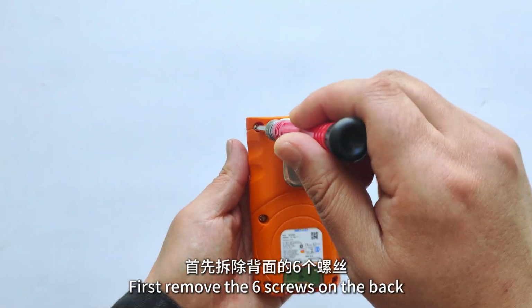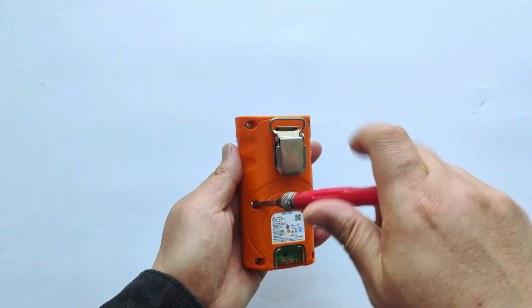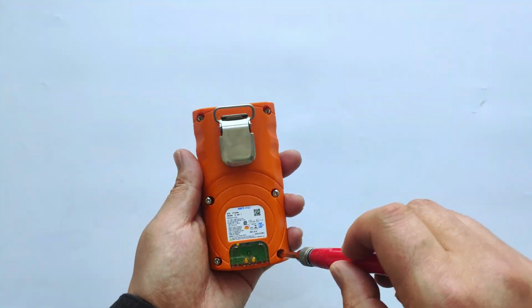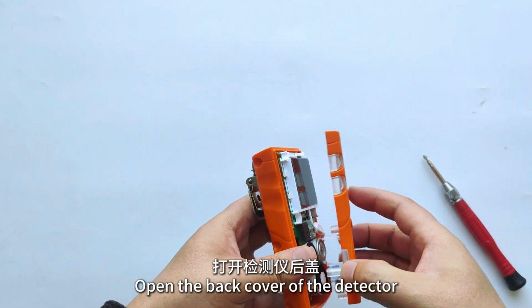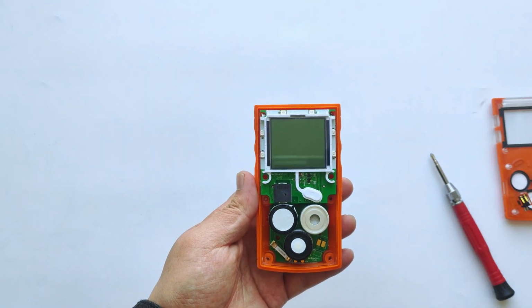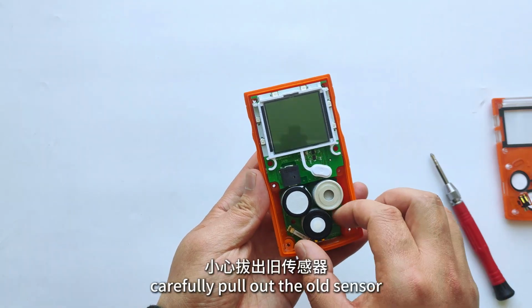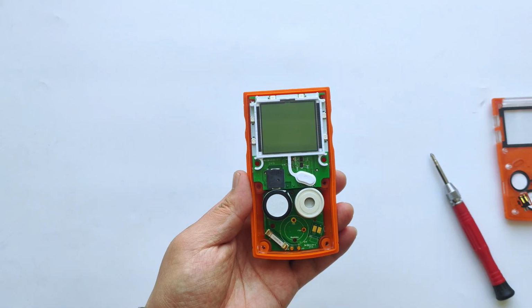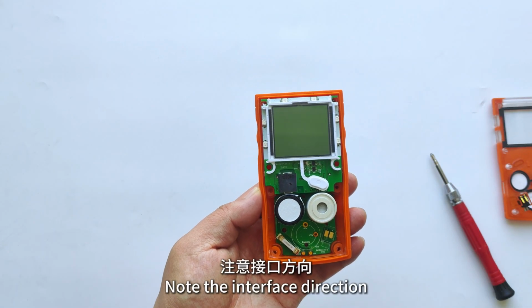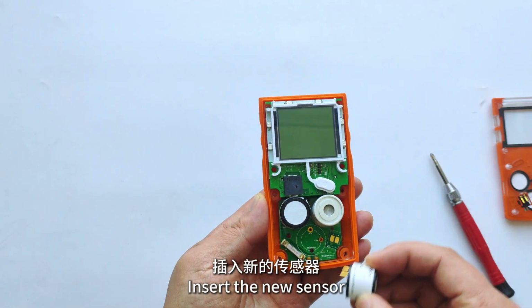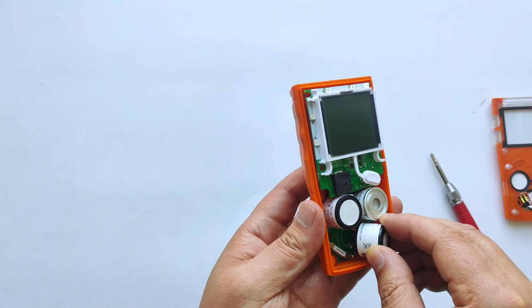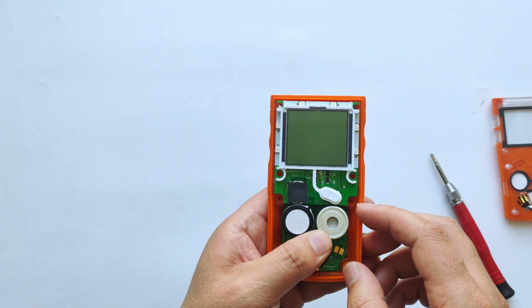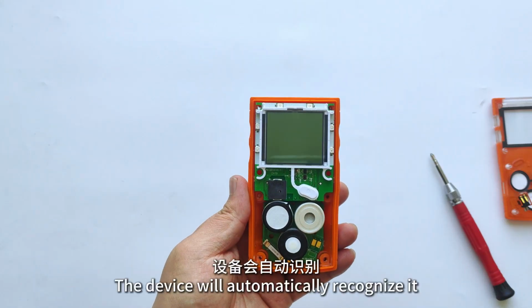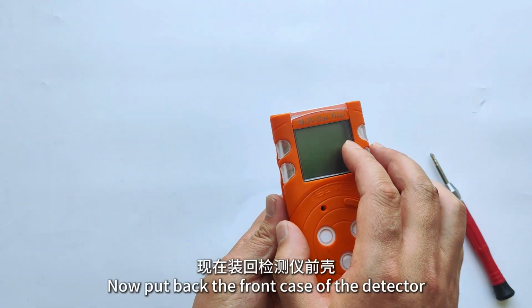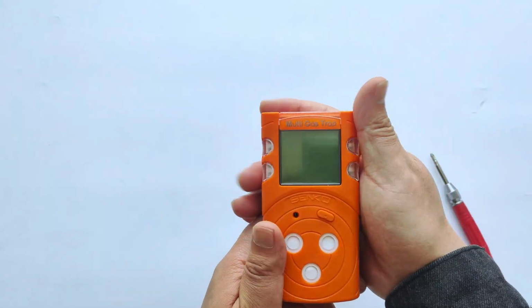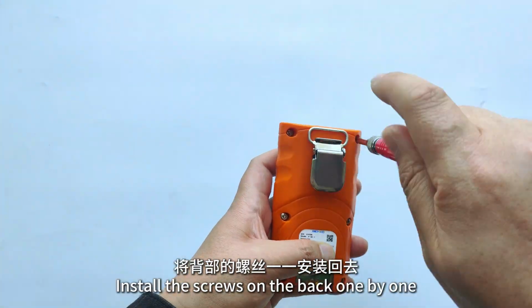First, remove the 6 screws on the back. Open the back cover of the detector. Carefully pull out the old sensor. Note the interface direction. Insert the new sensor. Make sure it's fully tightened. The new sensor is plug and play. The device will automatically recognize it. Now, put back the front case of the detector. Install the screws on the back one by one.